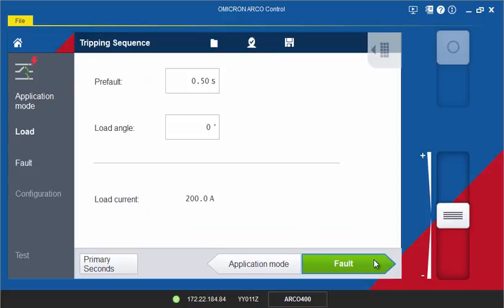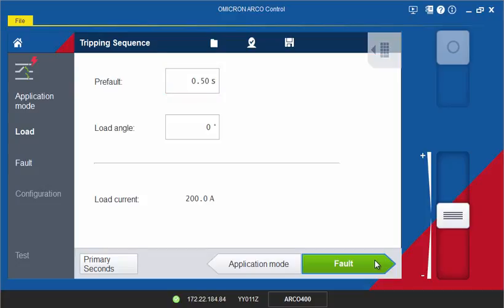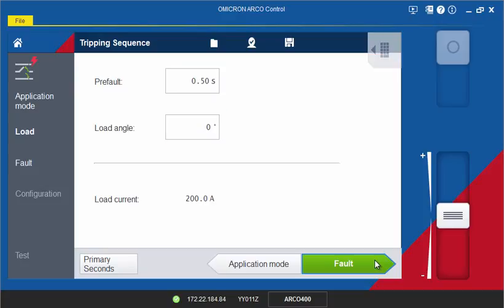In the following page, the load state can be defined. Enter the duration of the pre-fault state. A load angle can also be defined if the recloser control supports voltage inputs. The load current is automatically taken from the setting in the hardware configuration.